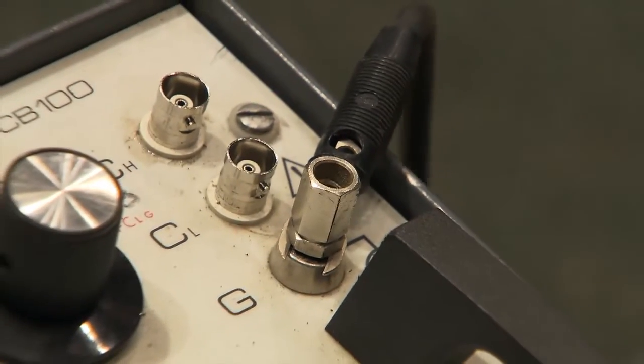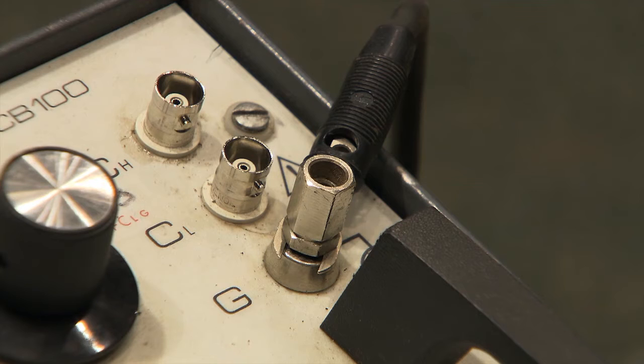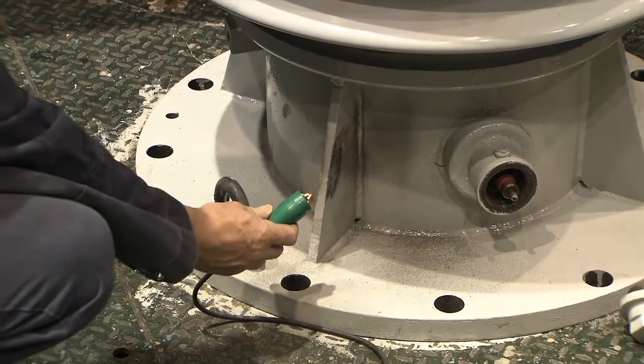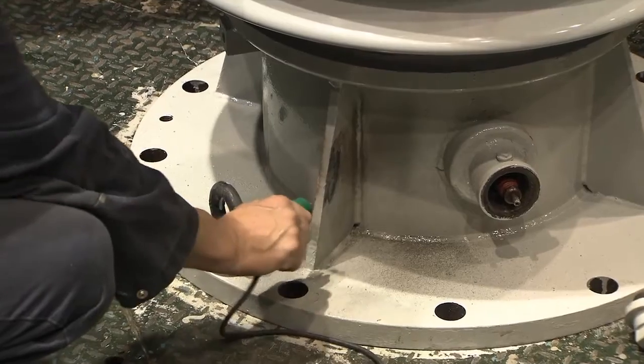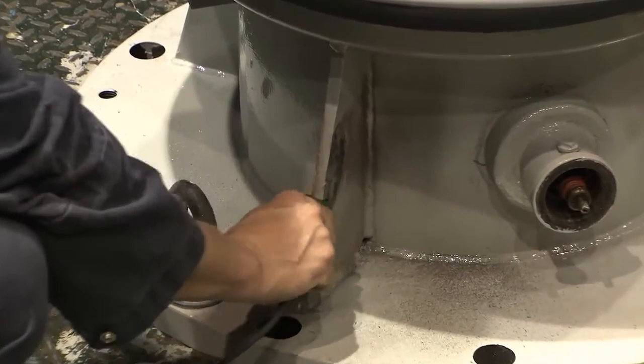The first test is the UST test that measures the integrity of the main insulation, also known as C1, between the conductor core and the winding that's connected to the capacitance tap. Connect one end of the ground lead to the terminal on the DF bridge. Connect the other end of the ground lead to the bare metal on the flange.